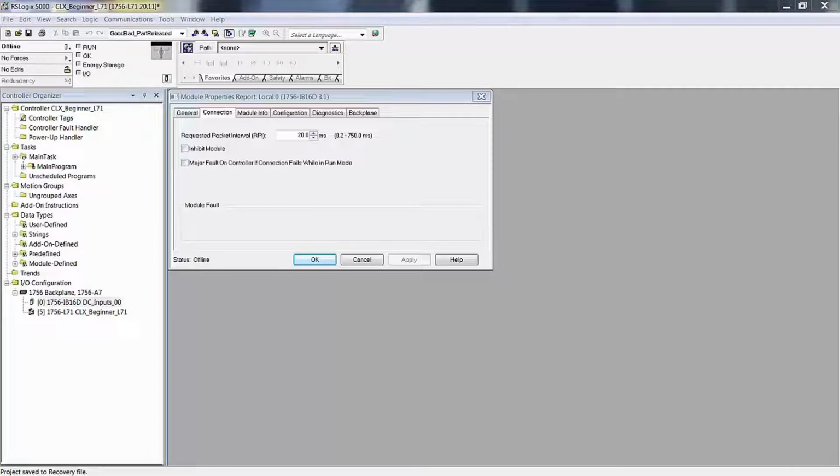Any of the MicroLogix products or SLC500 or PLC5, those are active backplane, meaning that the control of the backplane is an active process to collect inputs and hand out output states to the output modules. The controller actively controls the backplane for MicroLogix, SLC500, PLC5. With ControlLogix, the processor does not control the backplane. It is simply an entity to communicate across the backplane.